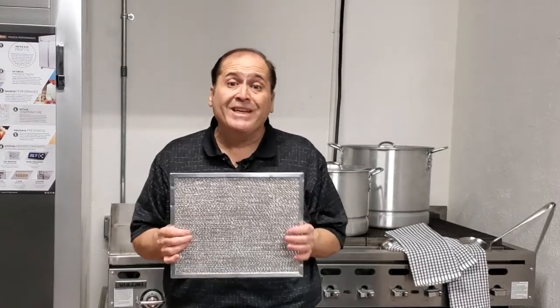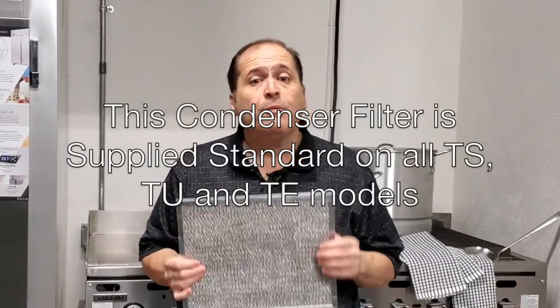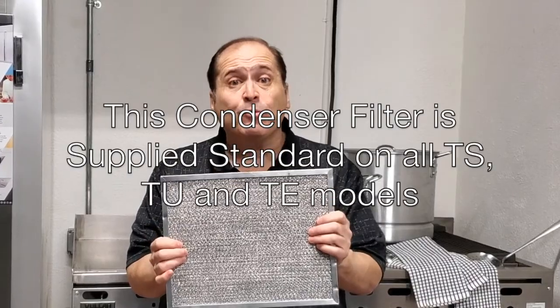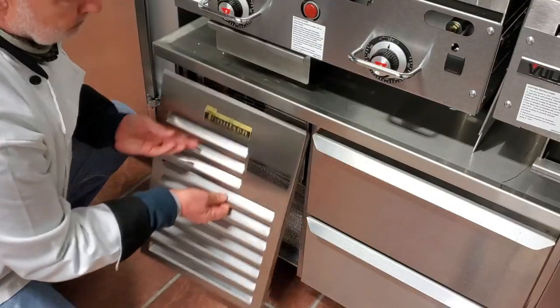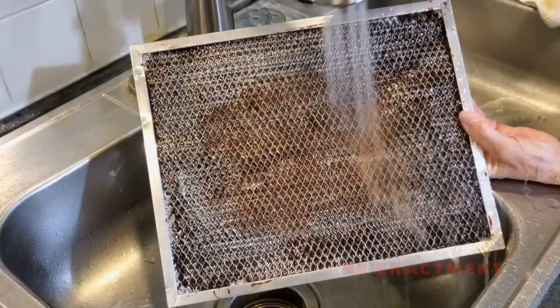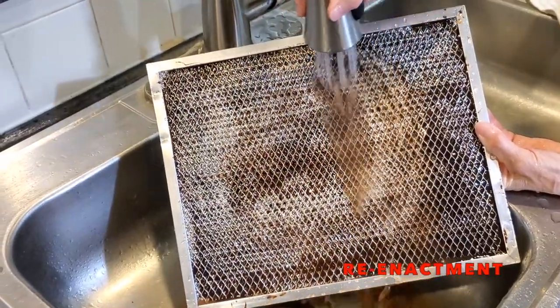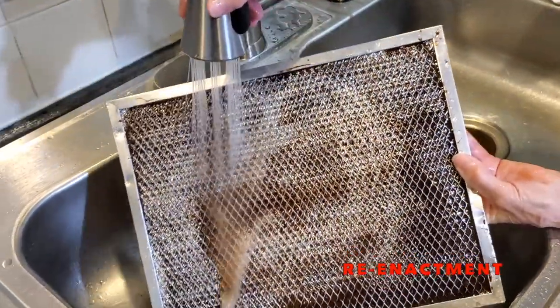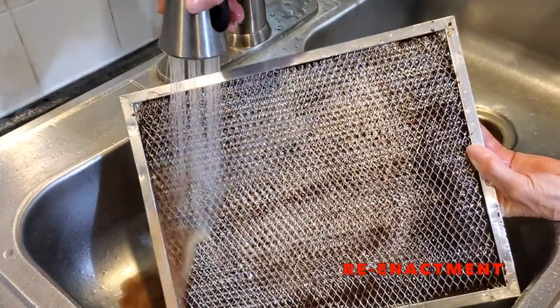Fortunately, there's no need to ever do this with a Traulsen refrigerated or freezer equipment base, because these include an easily removable filter. This captures grease and particulate matter, thus protecting the condenser coil from becoming clogged. In order to clean this, simply remove the louver panel and lift out the filter. This can then be taken to the sink, where it can be sprayed clean with hot water to remove any accumulated grease and debris. Allow this to air dry before replacing the cabinet and restoring power.